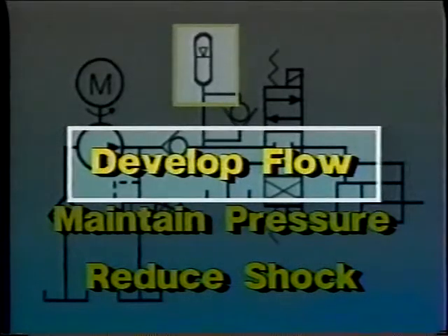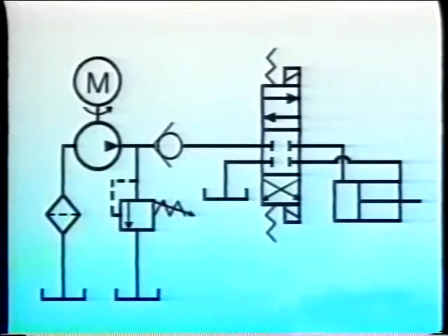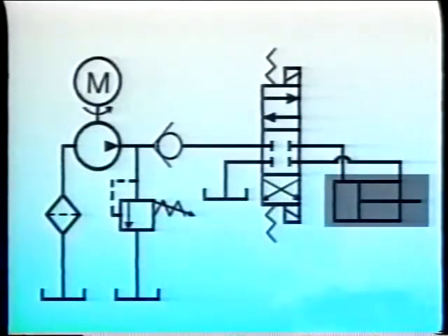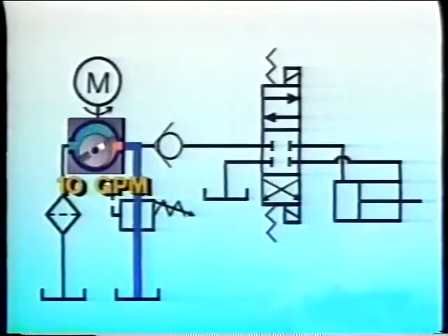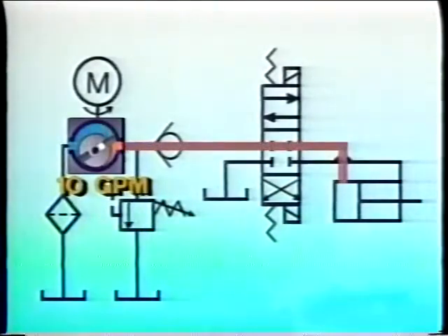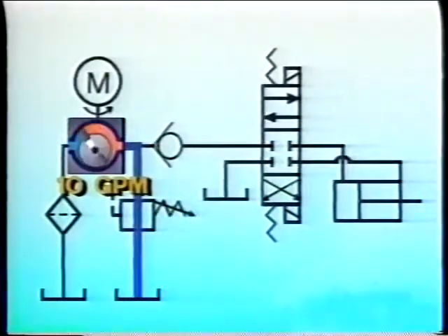Accumulators used to develop flow can increase flow when the demands of the system are greater than the pump can deliver. Suppose for example that a machine operates only once every 10 minutes but requires 10 gallons delivered in one minute. A 10-gallon-per-minute pump could be used, but it would idle for nine out of 10 minutes, work for a minute, then idle for another nine minutes. The pump and its motor would waste power idling.